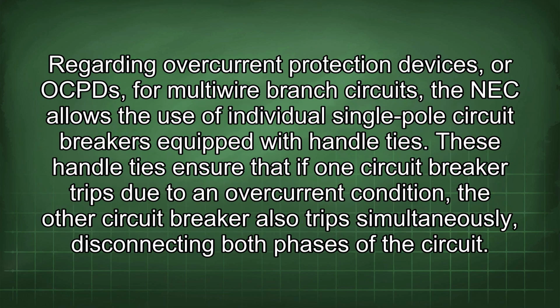Regarding overcurrent protection devices, or OCPDs, for multi-wire branch circuits, the NEC allows the use of individual single-pole circuit breakers equipped with handle ties. These handle ties ensure that if one circuit breaker trips due to an overcurrent condition, the other circuit breaker also trips simultaneously, disconnecting both phases of the circuit.